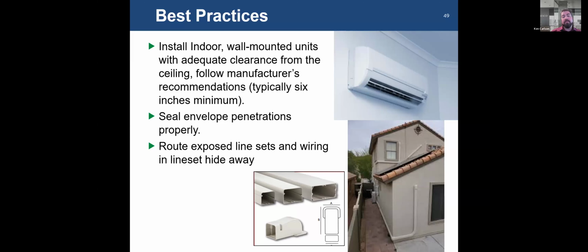Install your line set and wire. You can run your drain down into this as well. You just have to penetrate on the bottom, at a low point. Once all that is set, everything's been done, everything's been started, you can put your top cover on. You can even paint it if need be. They make penetration fittings as well, as shown in the bottom here, that can get screwed and mounted directly to the wall, and then that can be sealed tight so that you don't have any water infiltration.